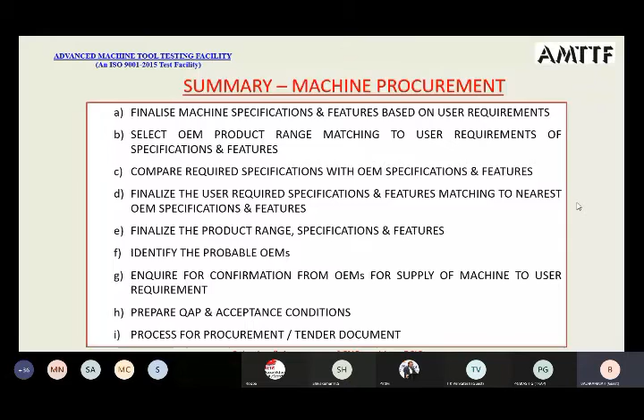The acceptance plan and inspection, relevant standards - the OEM has to comply with your requirement. Safety features you have to comply with, warranty you have to specify, and installation commissioning documents you must provide, such as what type of power supply, gas, and air supply you require.